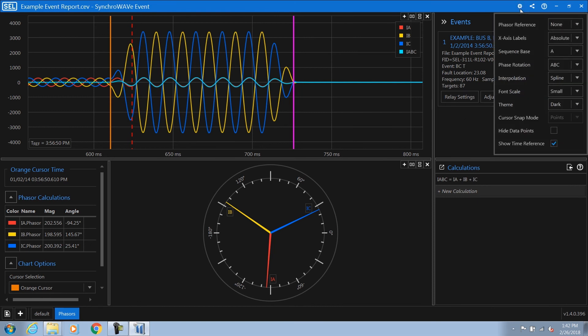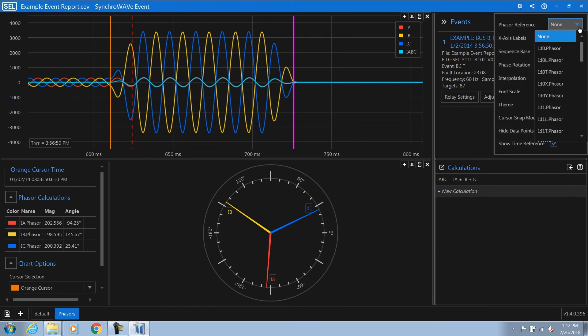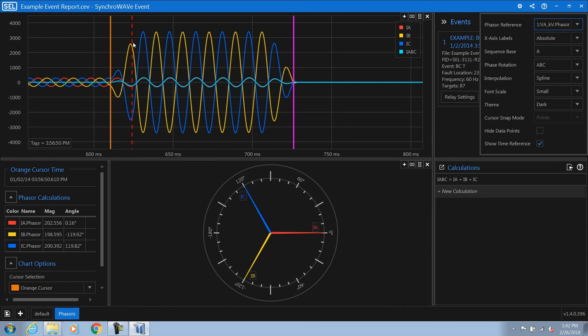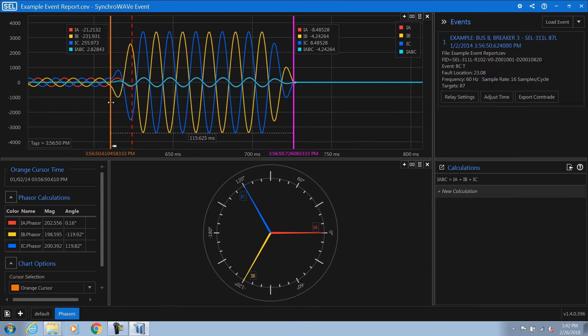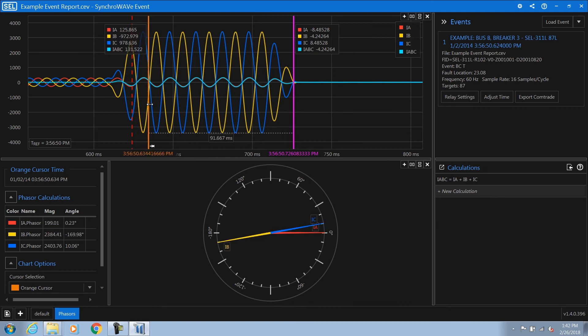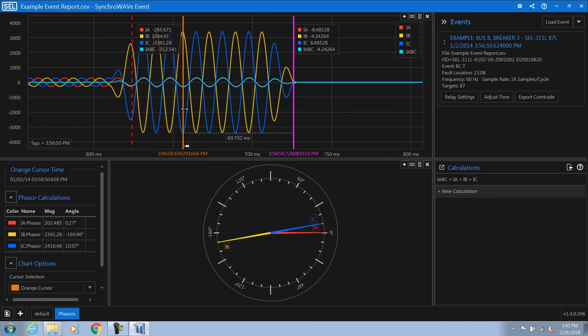The next thing that we need to do is set a phasor rotation for this. We can go to the global settings, choose my phasor reference, and select my A phase voltage. Now, as I grab and drag the orange cursor through the event, I can see how my current phasors rotate with respect to the event as I drag through time.